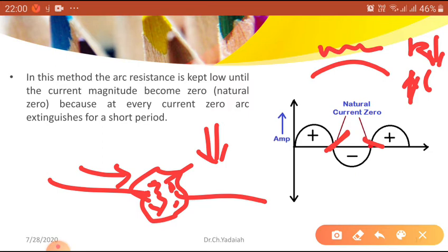Whatever air or oil is present between the contacts during this period has very little dielectric strength and is unable to oppose the flow of current. So the current passes through this low dielectric strength material, which breaks down under the voltage raised between the two electrodes. That sustains the arc for further cycles.